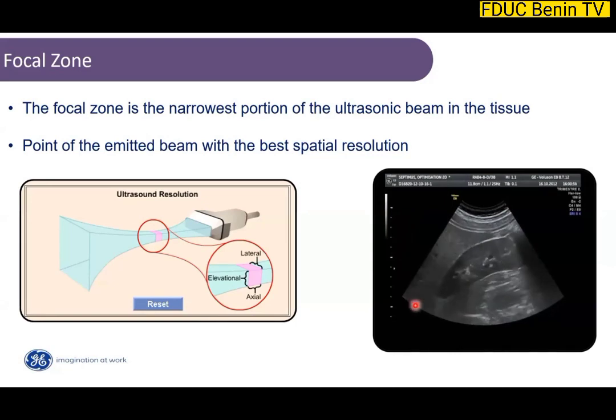And the more I'm moving this, you see that the image quality is impacted. I'm increasing the signal at the level of my focus. Why? Because when I'm moving my focus position, I'm telling the ultrasound beam to stop at this position and give me the best resolution possible, with as much of my ultrasound waves as possible at this specific position.